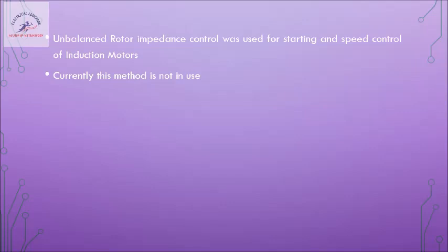Now because of the continuous use of motors, because of wear and tear or frictional reasons, it is possible that the physical structure of the rotor may change over time. The rotor bars are connected to the rotor rings, if you imagine the construction of a squirrel cage or a slip ring rotor. If there is a loose contact in the rotor circuit, and we are talking about a loose contact, not an open circuit, then it will alter the effective area of cross section of a conductor.